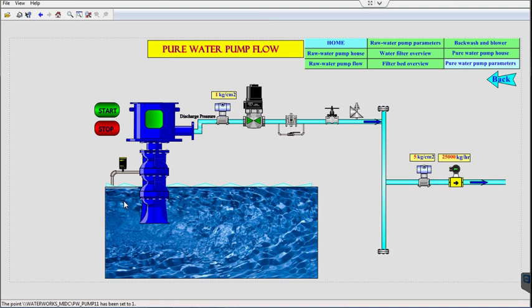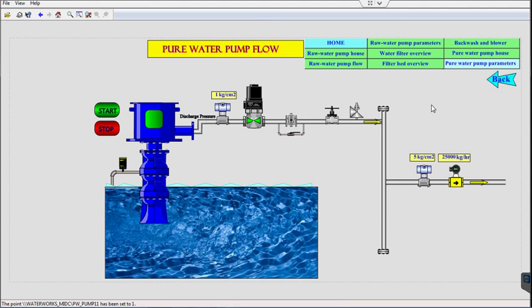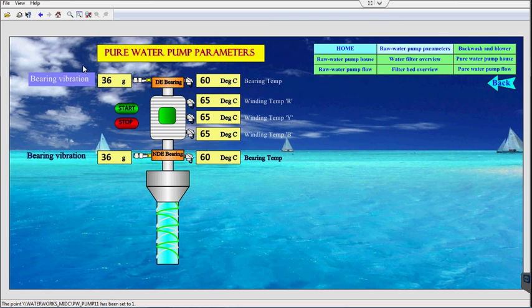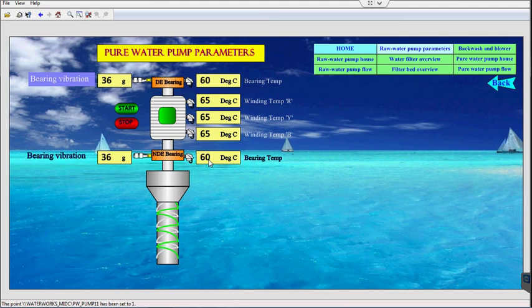Let us understand how pure water pump flow works. The pure water pump is provided with water from the pump sump for cooling and lubrication. A pressure switch is provided on each line to ensure lubrication of the pump bearings. When the pump is started, the discharge butterfly valve will automatically open. If an adequate amount of pressure is developed, the pump will continue in operation; otherwise it will automatically stop. Each pump is provided with a magnetic flow meter to calculate the pump performance. A dedicated master PLC and SCADA is designed for the pure water pump system, interfaced with the historian. Pure water pump safety is ensured by measuring pump bearing vibrations, pump bearing temperature, and motor winding temperature. These parameters are recorded in SCADA, and in case they exceed the allowable limit, an alarm will be raised to alert the operator to take precautionary action. These parameters can be further used for a machine maintenance monitoring system.